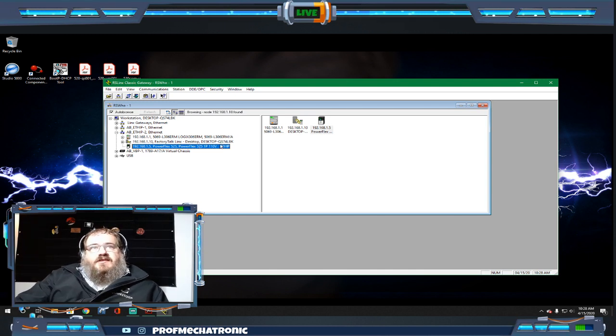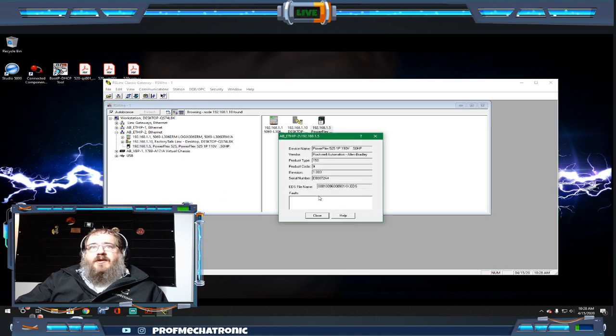Another advantage is it actually gives us a little bit of information about the PowerFlex drive itself. It's a 525, single phase, 110 drive, half horsepower. Now if you right click on the drive itself, you can look at the device properties. From there we can pull out the serial number, the revision, product code, type, all that stuff, and see if there's any ongoing faults on the drive right from RSLinx. You may see that the revision of this drive is pretty old. I'm doing another live stream where we're going to do a firmware upgrade on this one, so I've left this at revision 1.